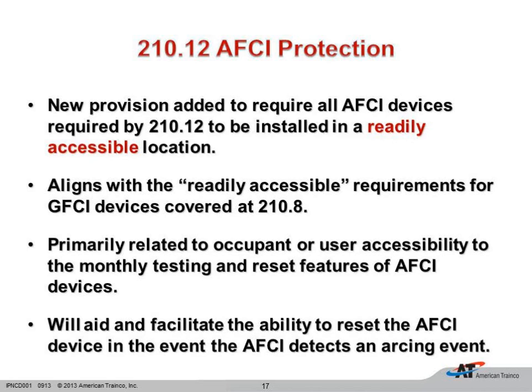So all of the 120 volt single phase 15 and 20 amp circuits in our residential buildings that supply outlets or devices. So "or devices" has been changed. That means that if we have another circuit in the bedroom, maybe we have a switch in that bedroom to control a fountain outside or some outside lights, and that switch is not part of that bedroom circuit, that switch will now have to be AFCI protected.